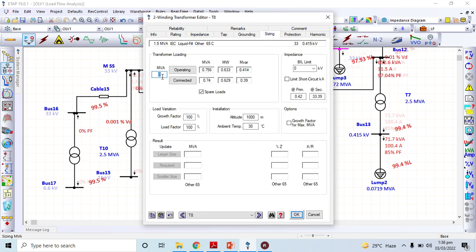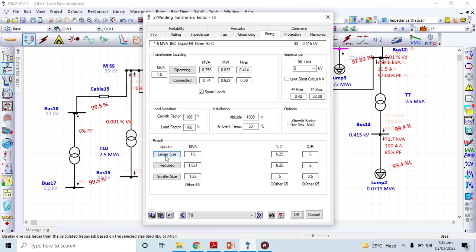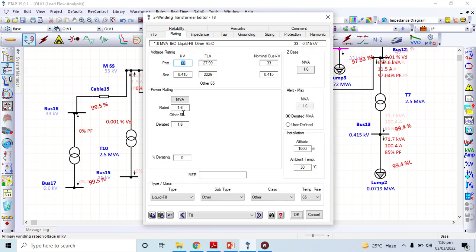Here I have transformer loading. It is on default — meaning whatever rating I give, 1.5 MVA is the connected load by default. I will mention 1.5 MVA as the rating of my transformer, but I want to overload it and use it at a larger size. So I click it to 1.6 MVA. You can see the rated value which was of 1.5 MVA is now converted to 1.6 MVA — this is the maximum capacity of overloading I can enforce on this transformer.